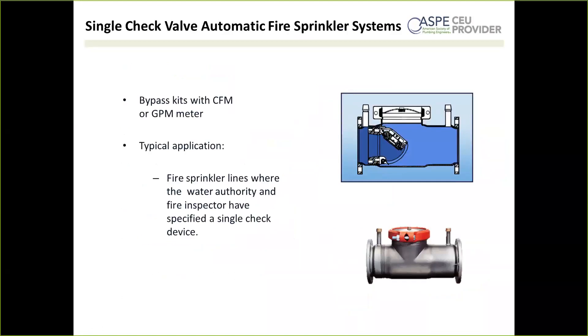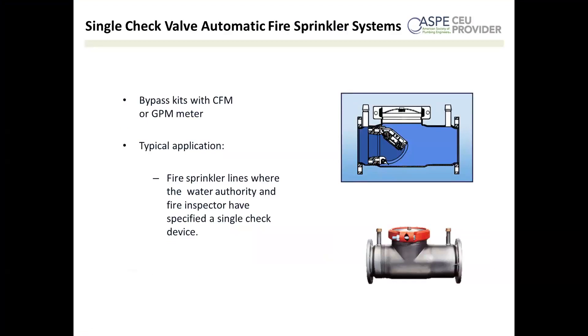Single check valves for automated fire sprinkler systems are included because they are relatively common, but they are not true backflow preventers — a single check is not a backflow preventer. They sometimes come with a metered bypass, and are sometimes okayed by the water authority and fire inspector for sprinkler lines, but for the most part they exist because they are grandfathered in. They are being replaced more and more with actual backflow preventers.